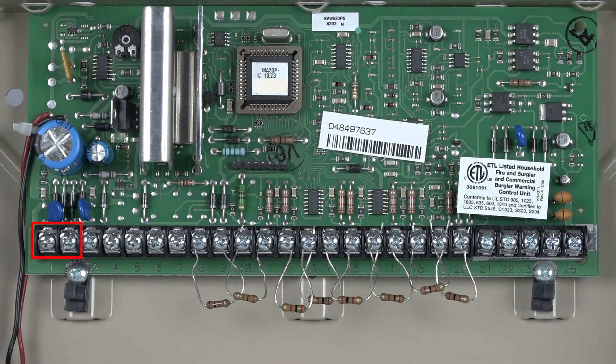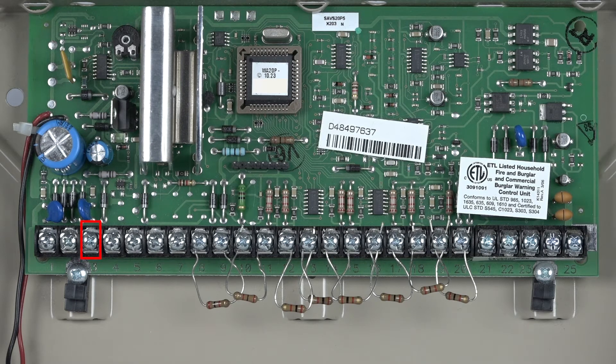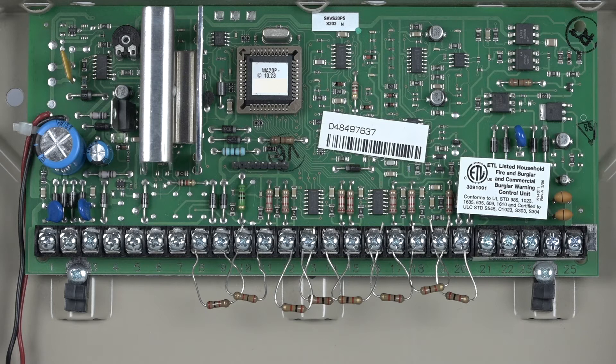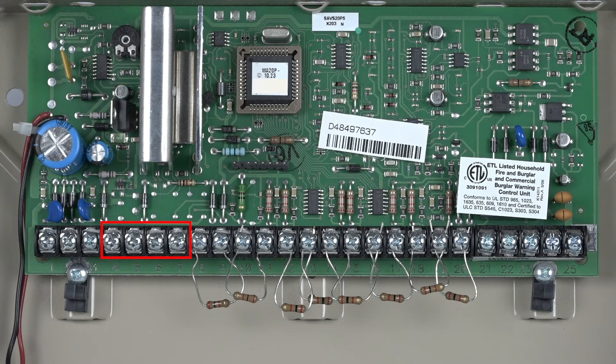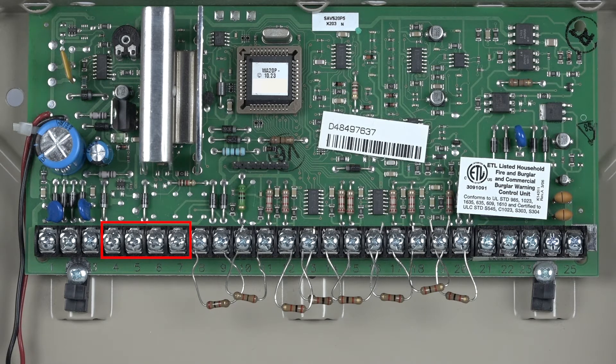Terminals 1 and 2 are for AC power. Terminal 3 is the positive connection for your bell. Terminals 4 through 7 is your ECP bus. This is where all ECP devices such as keypads, a radio, and a wireless receiver are connected.